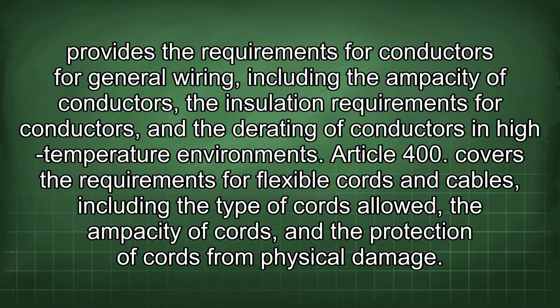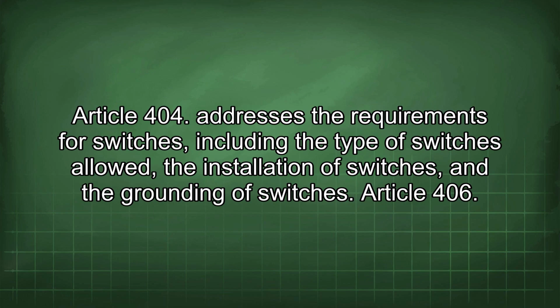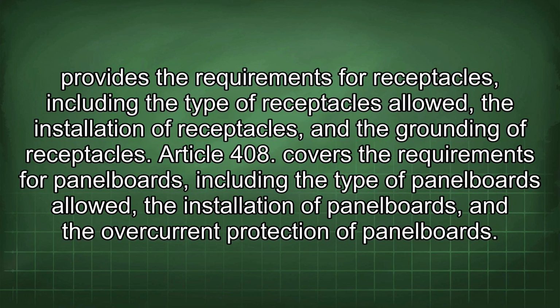Article 400 covers the requirements for flexible cords and cables, including the type of cords allowed, the ampacity of cords, and the protection of cords from physical damage. Article 404 addresses the requirements for switches, including the type of switches allowed, the installation of switches, and the grounding of switches. Article 406 provides the requirements for receptacles, including the type of receptacles allowed, the installation of receptacles, and the grounding of receptacles. Article 408 covers the requirements for panel boards, including the type of panel boards allowed, the installation of panel boards, and the overcurrent protection of panel boards.